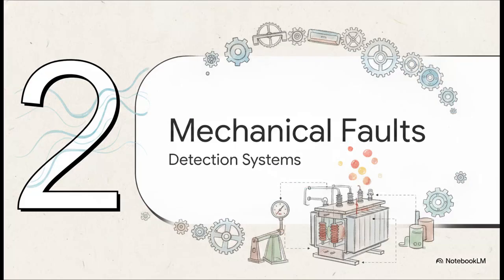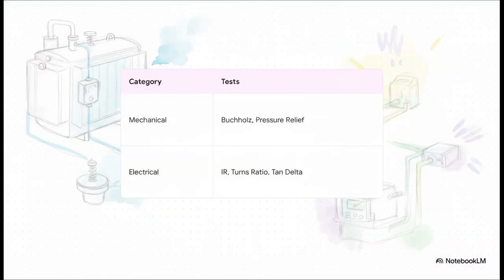Moving right along to Section 2, Mechanical Fault Detection Systems. So, there is a very clear division between our mechanical safeguards and our electrical tests. On the mechanical side of things, we've got devices like the Buchholz relay that covers both the main tank and the on-load tap changer, plus pressure relief valves. These mechanical components act as our first line of defense. They physically react to gas buildup or sudden pressure spikes way before we even start testing the internal electrical insulation.